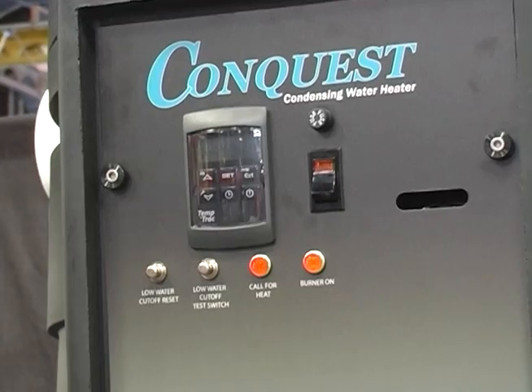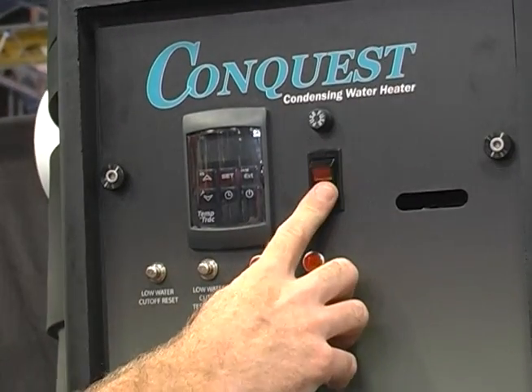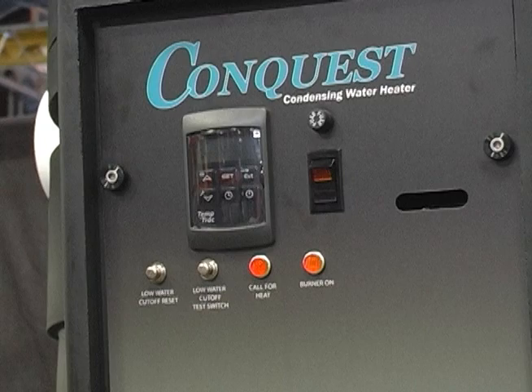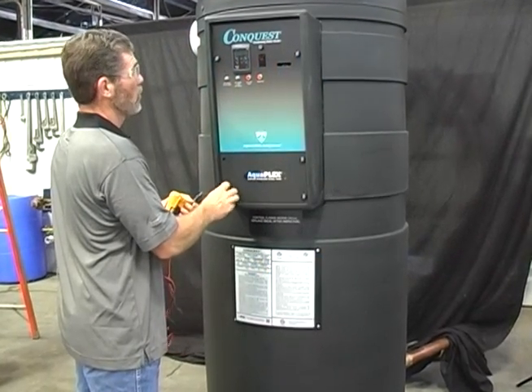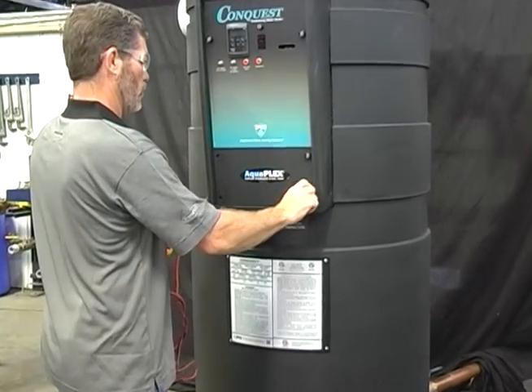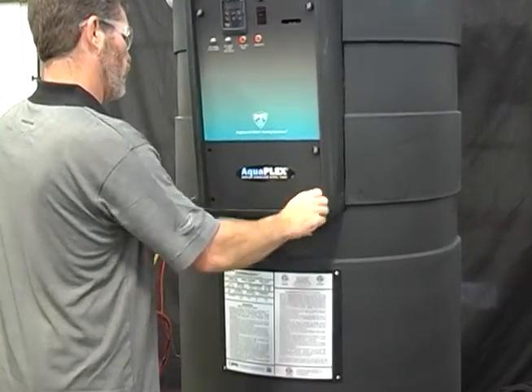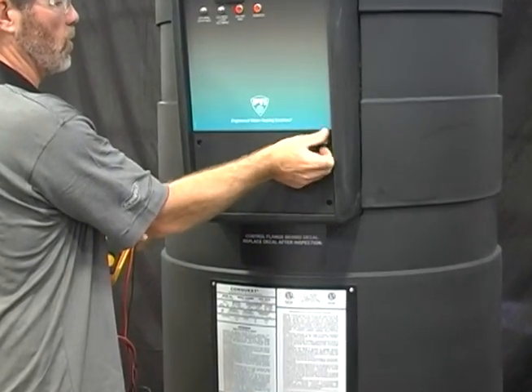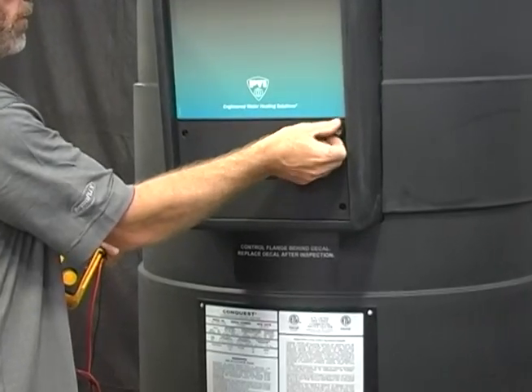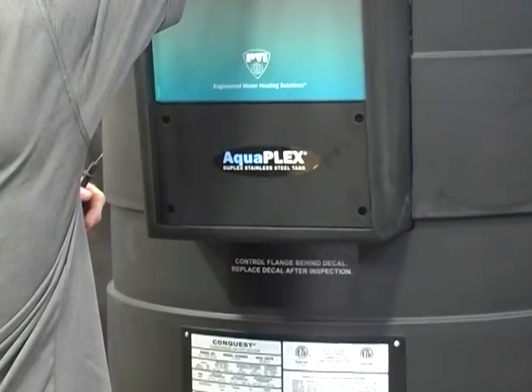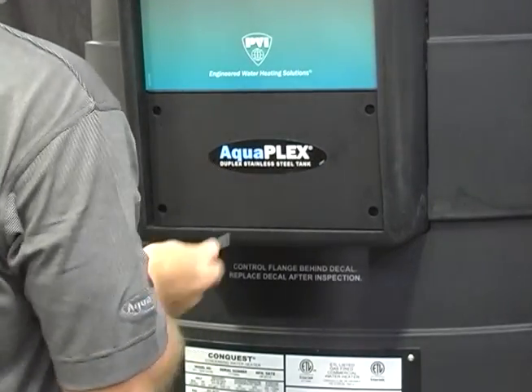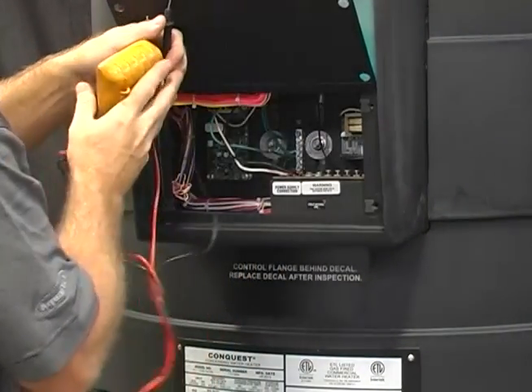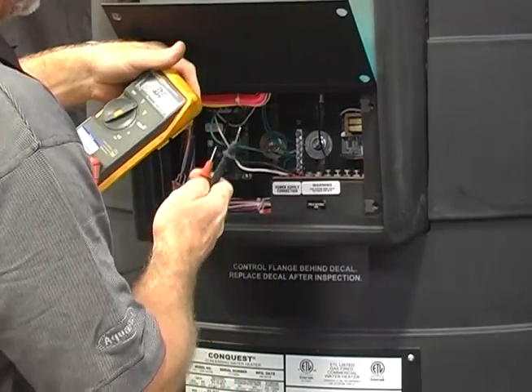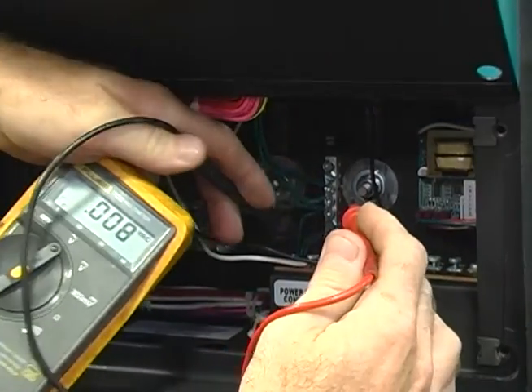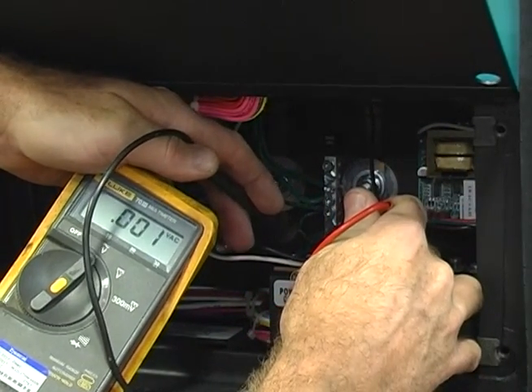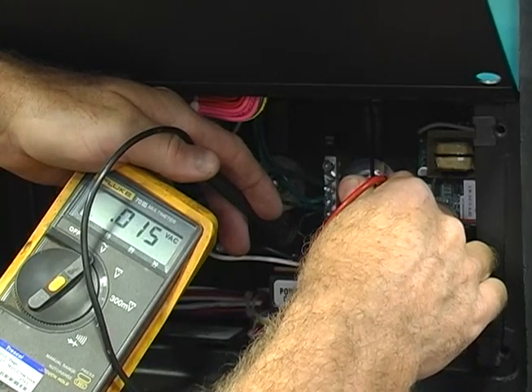On the water heater's control panel cover, move the electrical rocker switch to the off or down position. Remove the panel screws to open the hinged bottom control enclosure cover to expose the main terminal strip. Before continuing, confirm that power is not connected to the water heater. Use a multimeter to check across terminals L1 and L2. The 120-volt power connection is made to terminals L1 hot and L2 neutral. The operating control on the water heater is polarity sensitive, so you must ensure that the power is wired correctly to terminals L1 and L2. Also verify that the ground wire is secured to the grounding lug.